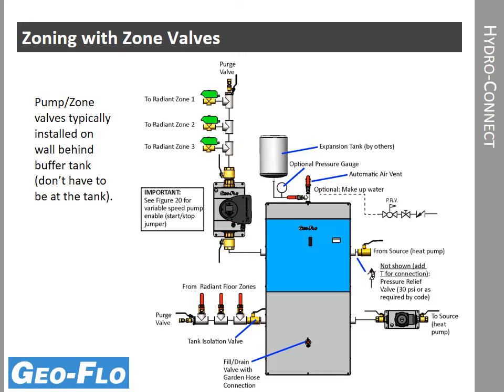And each one of those zones, each one of those radiant manifolds, in the case of a radiant system, or each fan coil, if we had fan coils per zone, would have a zone valve that's going to turn on and off based on that zone's call from the thermostat. The variable speed pump just below that header is designed for differential pressure. So as the zone valves open and close, the pump speeds up and slows down. And that allows us to dial in the exact flow rate based on the number of zones calling.